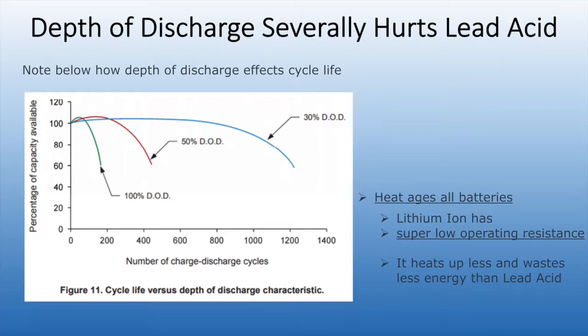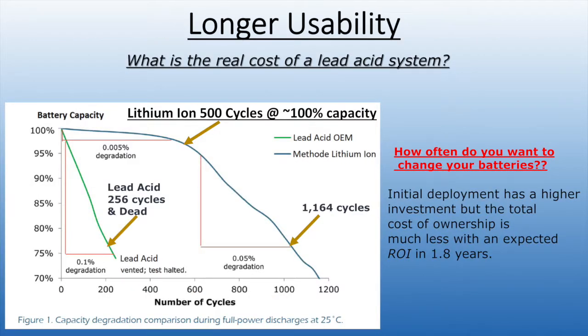All heat hurts all batteries, and lead acid actually has a higher internal resistance, so it heats up more, and that causes lead acid also to wear and lose capacity faster. This chart further shows the devastation that lead acid has from its cycling. As you can see from the chart, lead acid actually loses capacity as you go through cycles. On the left-hand side of this chart, you can see that at about 75%, 25% of the capacity is lost by the time you get to 256 cycles, which is basically considered dead for lead acid.